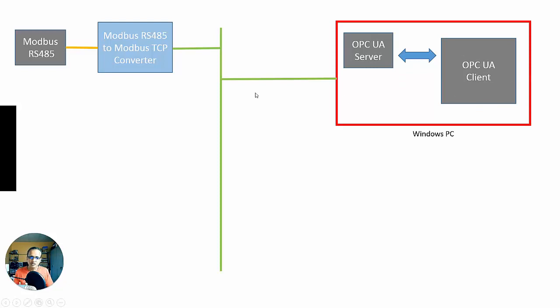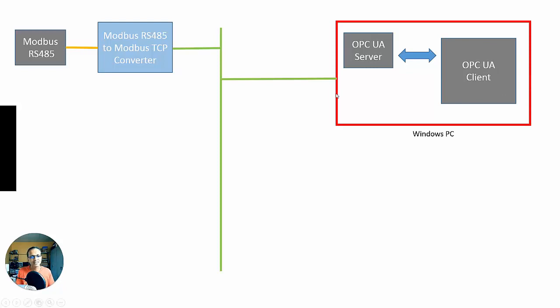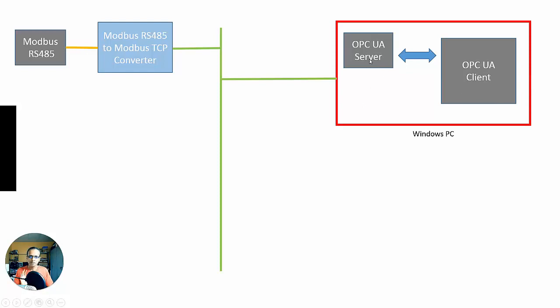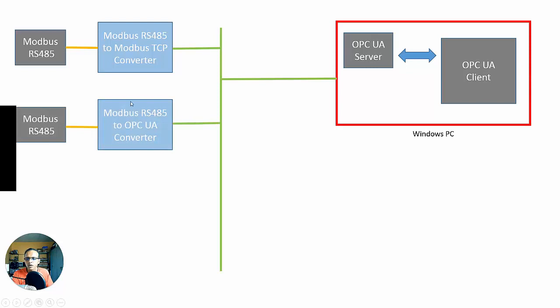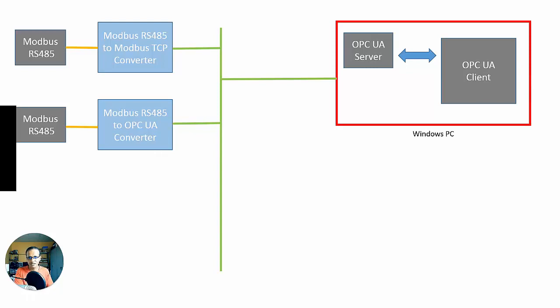Okay, so this classic OPC architecture is still in use today. In fact, if you look at most OPC UA server and client implementations, this is where you're going to be seeing OPC UA server being a really cool protocol converter. But with OPC UA, you could have other scenarios, like this one here. If I want, I could actually get now on the market, just type into the Google Modbus 485 to OPC UA converter. You're going to get tons of stuff.